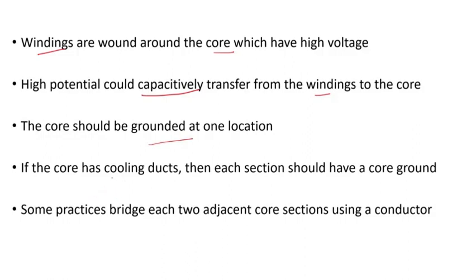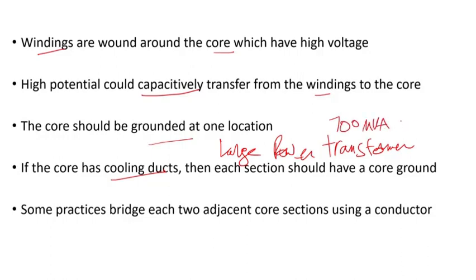If the core has cooling ducts, which is the case for large power transformers, so if you take, for instance, 700 MVA, 345 to 138 kV, or it can be anything, that's what I mean by large power transformers. So for those, the core is really huge. The cross-section area of the core is huge. So it's a big mass, even if they are laminated, but there is no cooling in between the laminations.